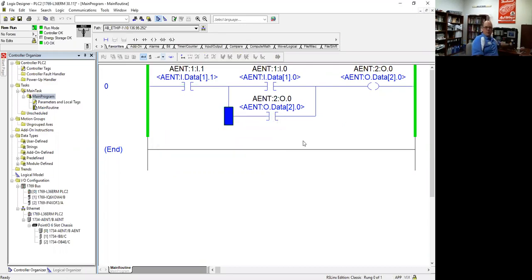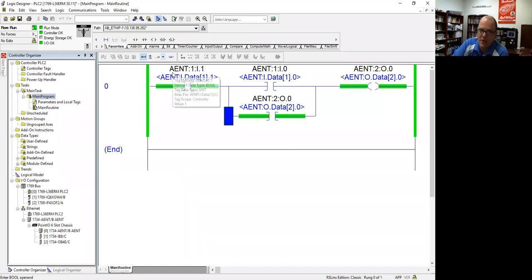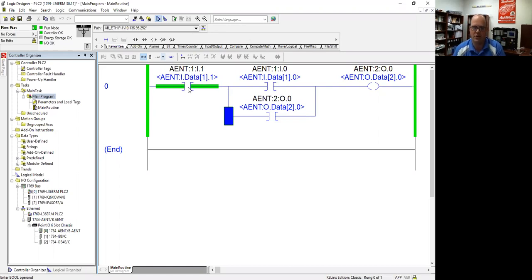I'm going to put on my selector switch simulating a normally closed stop button — when it's normally closed, power is passing through and the input is on. Now I'll download this. All I have to do is hit this push button for a tiny second and that keeps the light on, allowing a momentary signal to keep the output engaged. If I want to turn it off, I flip off the selector switch. Please remember: if you seal in a bit, always have some way to drop it off or turn it off.